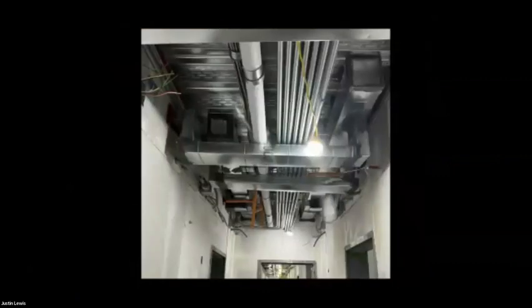Here's a good one too. If you look close right there, we can zoom in and you'll see that transition. Now, what's interesting about this is that the air is going to run past that transition, hit that back wall, and then be forced backwards and then up 90. Now, that's a huge pressure loss. And this is a low velocity, but we see this a lot of times on higher velocity systems on main ductwork, and the turbulence it creates just kills the performance.